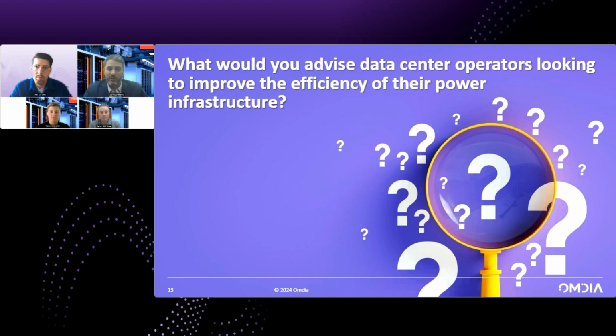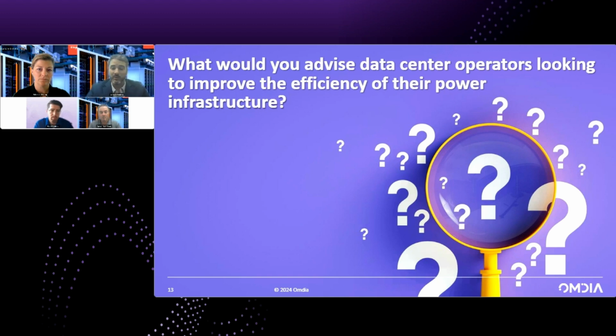The second part of your question is at the rack level, how do we monitor that? We take what we call our tap-offs, which is the power distribution of the branch circuit off of the busways, and we can monitor at each individual outlet. So we can say A run, B run, maybe there's multiple outlets on the tap-off. We can take a look at each one of those and give you revenue grade energy data.